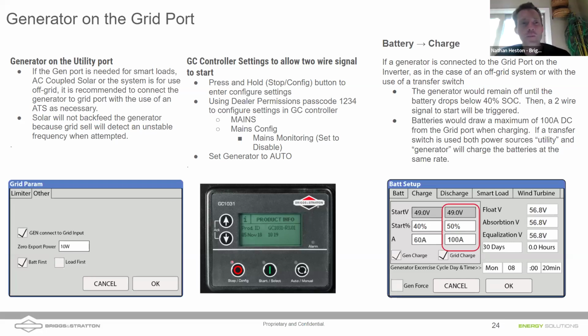So Daniel, on the left side of the screen, you were getting into it before I interrupted you, but I wanted to let John know that absolutely we can do off-grid, and that's important to us. On the left side of the screen, you're looking at the grid settings in the Sol-Ark, and you see a couple of things there. One, you've got that checkbox for a generator connected to grid input. You want to check that box if you've got the generator connected to grid input, either because you're off grid and you have no utility, or because you have a transfer switch and you still have a generator connected to the utility there.